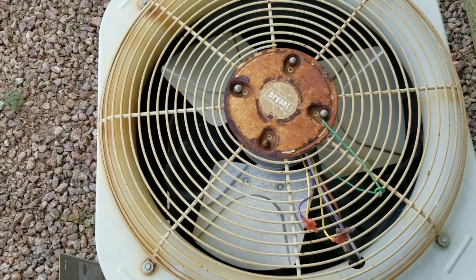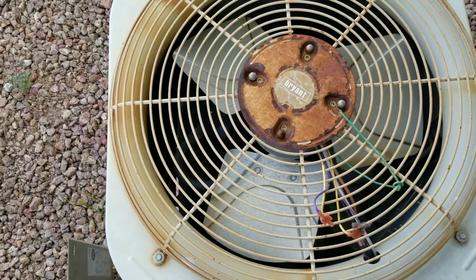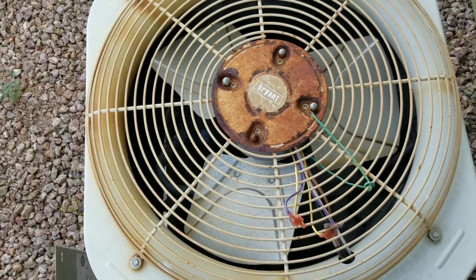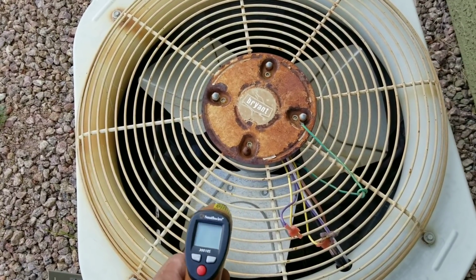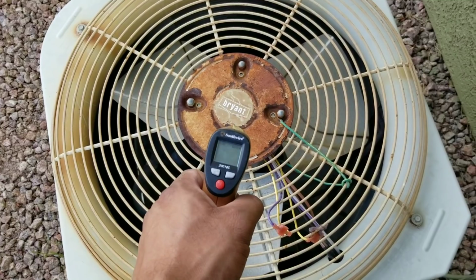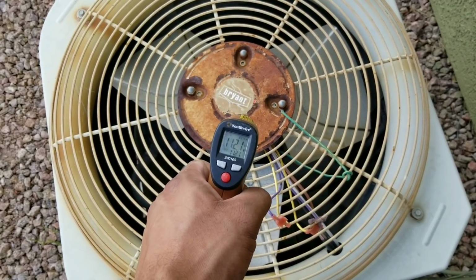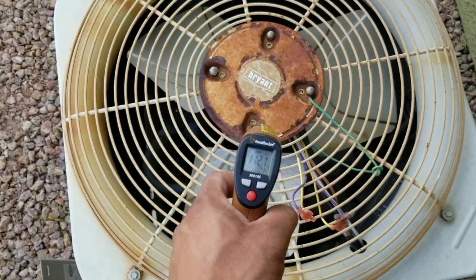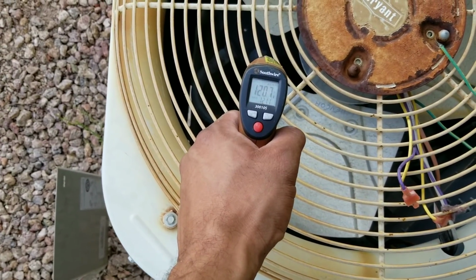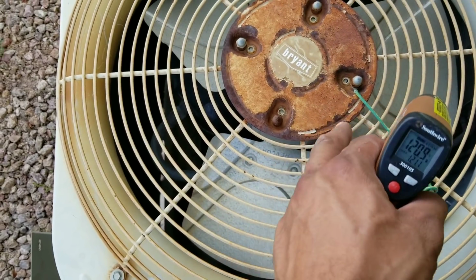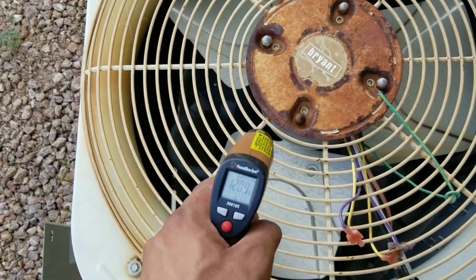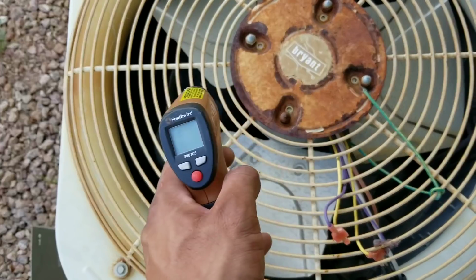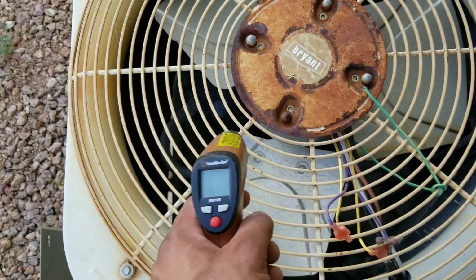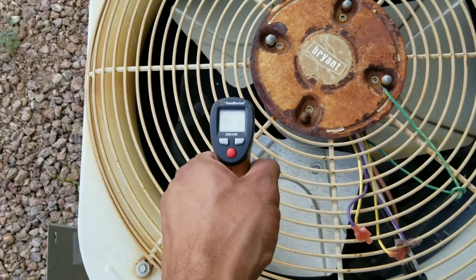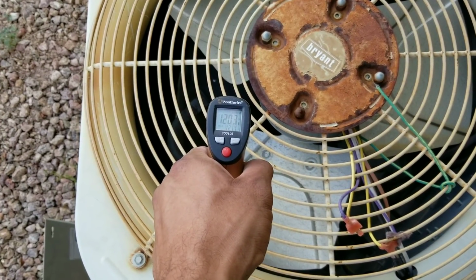What I want to do at this point is see if my compressor is overheated, and here I just have my temp gun. What I like to do is often just take the temperature of the fan motor. The fan motor is 112 degrees while it was running, and the compressor is reading 120 degrees. Whenever your fan motor overheats or fails, or your compressor fails, you'll know because you'll take the temperature. Obviously it'll range depending on the ambient temperature. I've seen them go up to 200 while overheated.